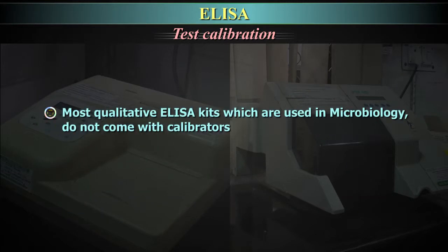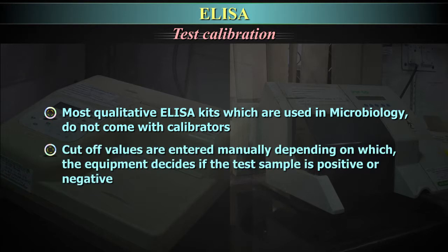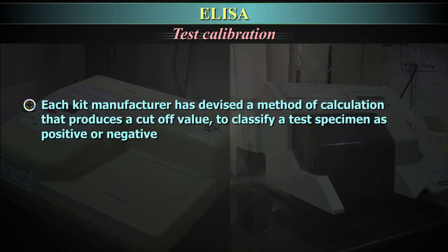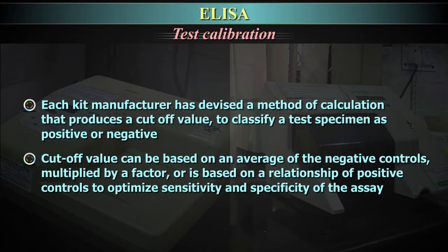Most qualitative ELISA kits used in microbiology do not come with calibrators. Cut-off values are entered manually, depending on which the equipment decides if the test sample is positive or negative. Each kit manufacturer has devised a method of calculation that produces a cut-off value to classify a test specimen as positive or negative. Thus, a cut-off value can be based on an average of the negative controls multiplied by a factor, or is based on a relationship of positive controls to optimize sensitivity and specificity of the assay.